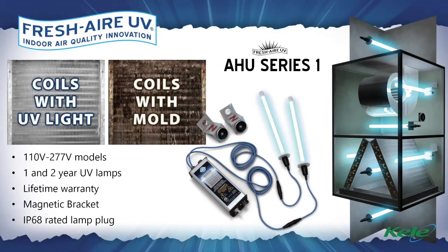It's a small footprint. It's a power supply, a commercial power supply that could fire additional smaller lamps. It is a small format UV system, typically up to 16-inch lamps. This is great for those light commercial, smaller systems, maybe up to 5 tons. You see there an example of an air handling unit. You would never have as many UV lights as you see there, but it gives you an understanding of the different strategies and different locations you can mount the UV system.